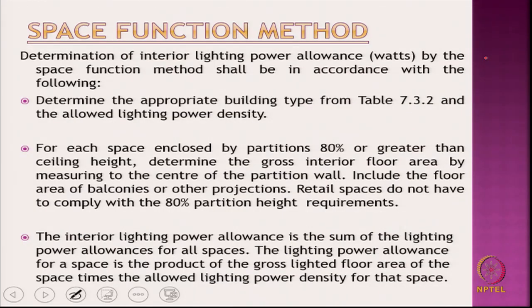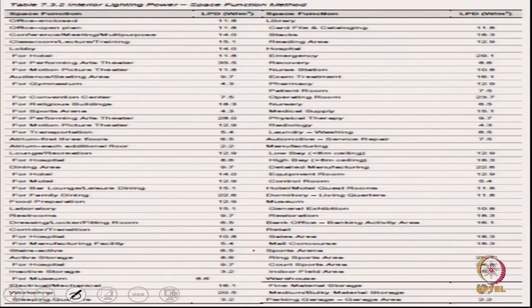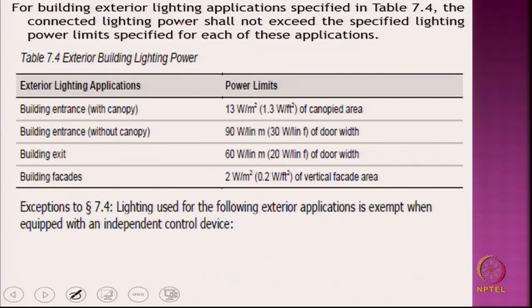Okay. In some cases you can find out the lighting through the space function method. Determine the appropriate building type, again from a table. Each space enclosed by partitions is 80% or greater than the ceiling height. Determine the gross interior floor area by measuring to the center of the partition, and include the floor area of balconies and other projections. Retail space does not have to comply with the 80% etc. So, the interior lighting power allowance is the sum of the lighting power allowances for all spaces, and this is again given in another table. So, here again the lighting power demand for interior lighting that is required is given.